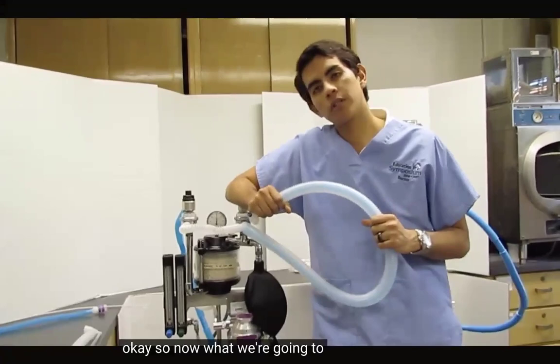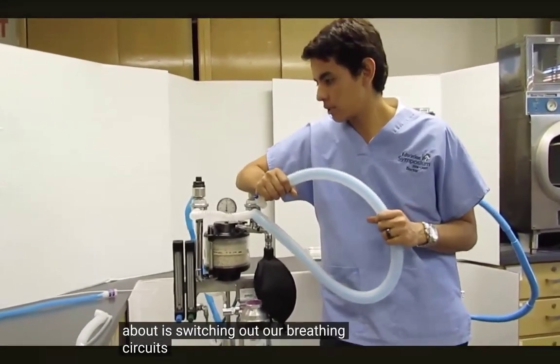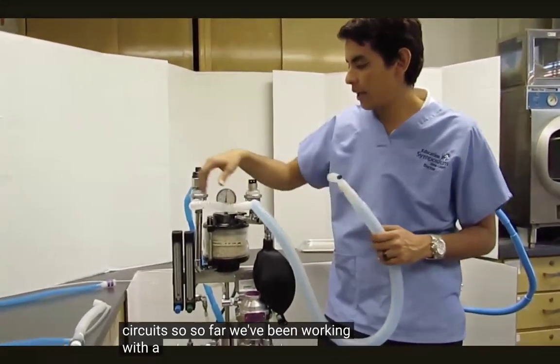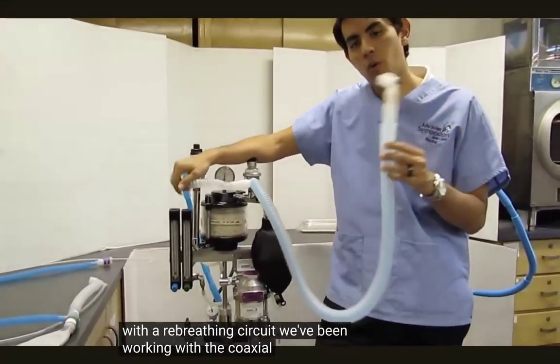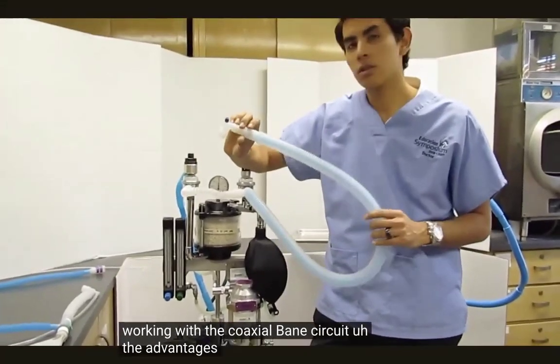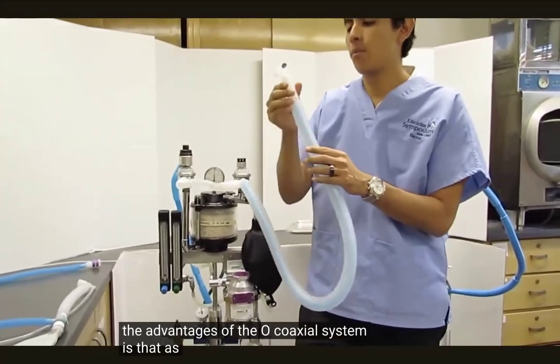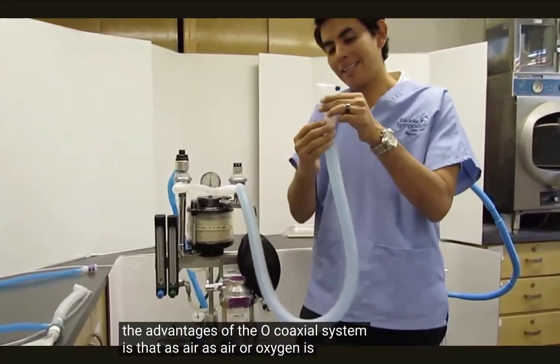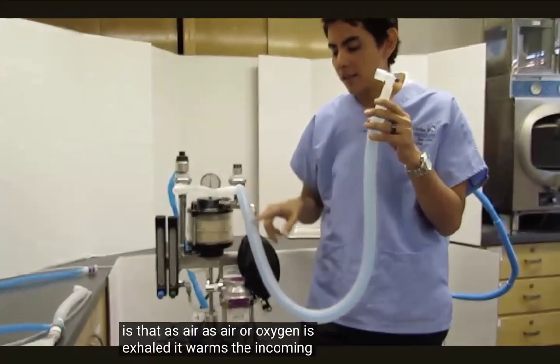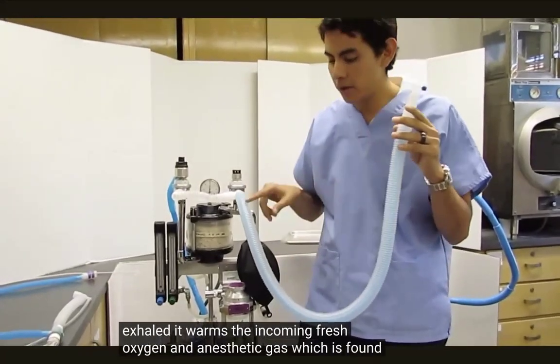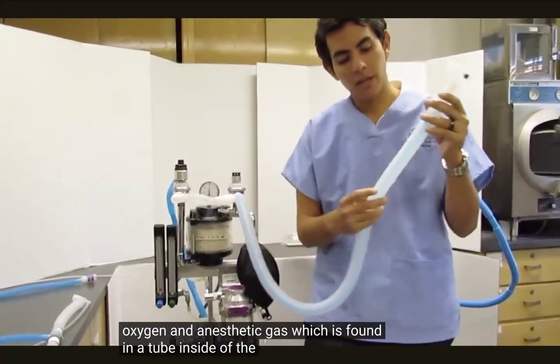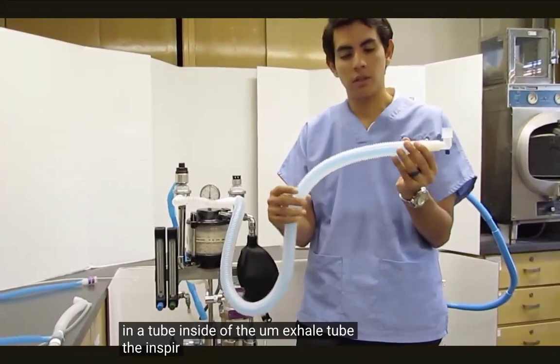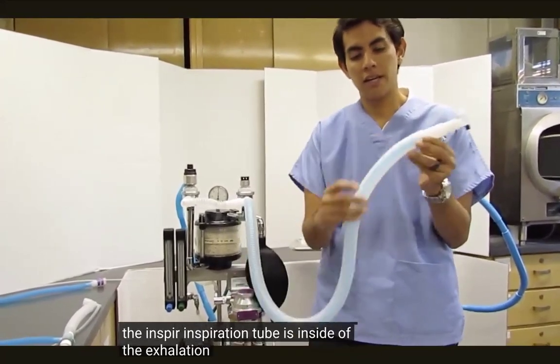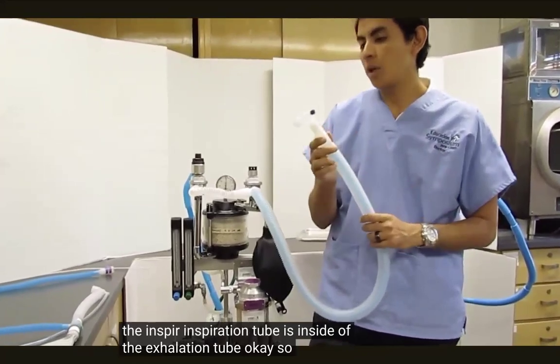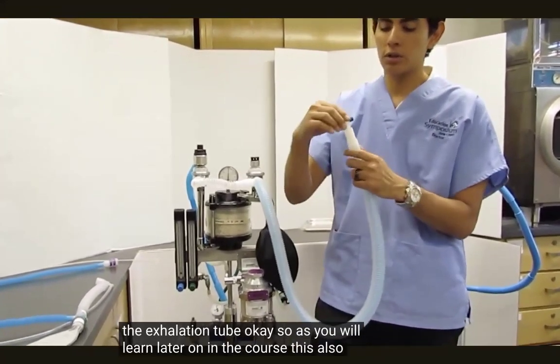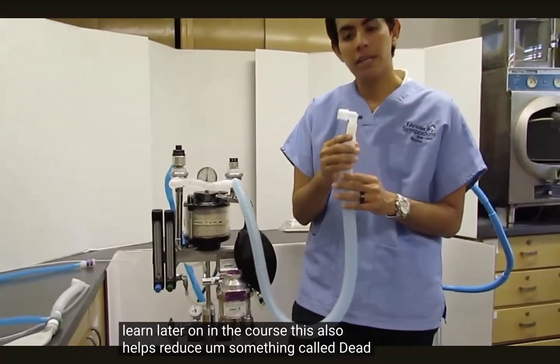Okay, so now what we're going to talk about is switching out our breathing circuits. So far we've been working with a rebreathing circuit. We've been working with the coaxial Bain circuit. The advantage of the coaxial system is that as air or oxygen is exhaled, it warms the incoming fresh oxygen and anesthetic gas, which is found in a tube inside of the exhale tube. The inspiration tube is inside of the exhalation tube. Okay, so as you will learn later on in the course, this also helps reduce something called dead space.